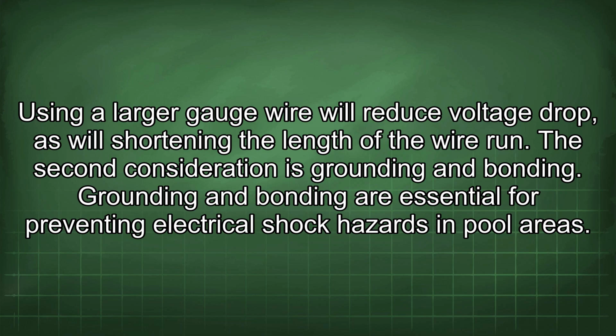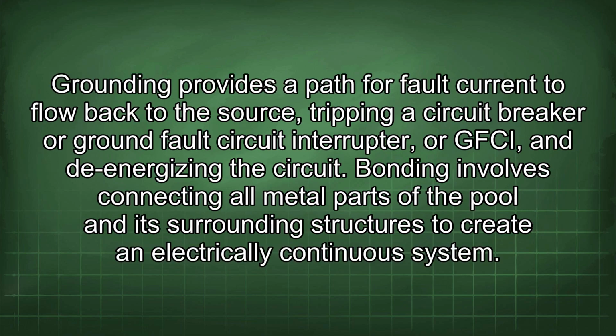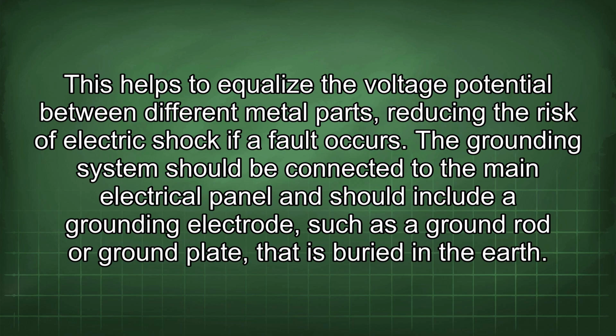The second consideration is grounding and bonding. Grounding and bonding are essential for preventing electrical shock hazards in pool areas. Grounding provides a path for fault current to flow back to the source, tripping a circuit breaker or ground fault circuit interrupter, or GFCI, and de-energizing the circuit. Bonding involves connecting all metal parts of the pool and its surrounding structures to create an electrically continuous system. This helps to equalize the voltage potential between different metal parts, reducing the risk of electric shock if a fault occurs.